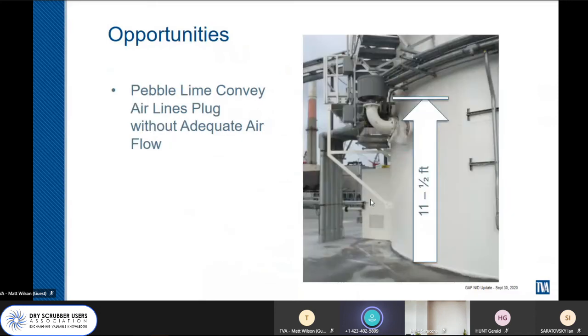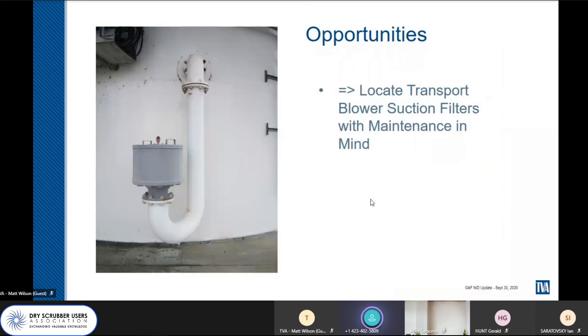This is an easy one. Pebble lime conveyor lines plug without adequate airflow. We learned this. So here was the intake filter. It's 11 feet above the ground. It's hard to get a change out on this, and it's hard to tell when it needs changing. So this is where Gallatin moved it to. Now it's nice and accessible down at the bottom, and you can see the differential across this air intake when the manual differential gauge pops.